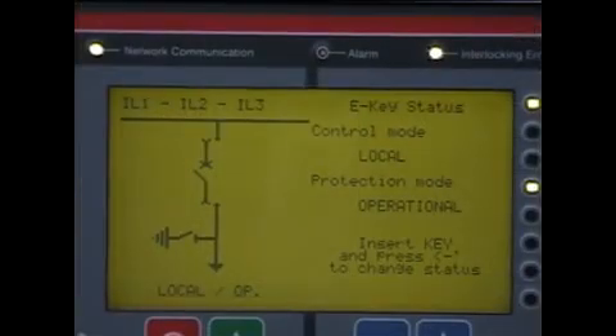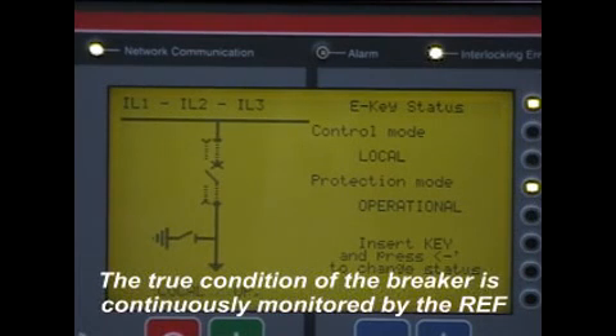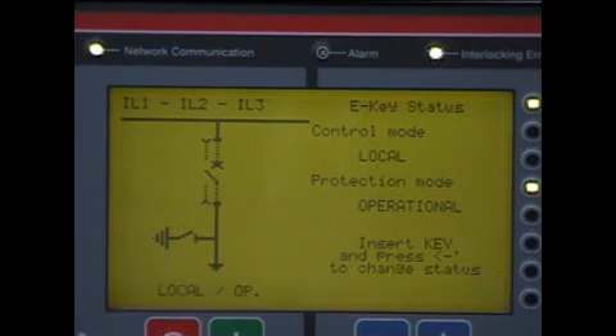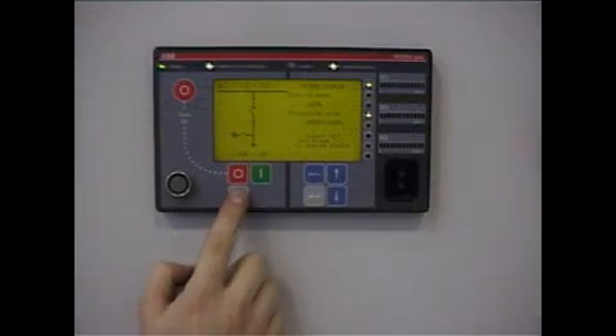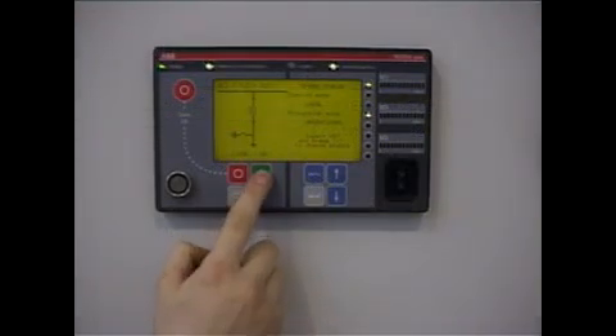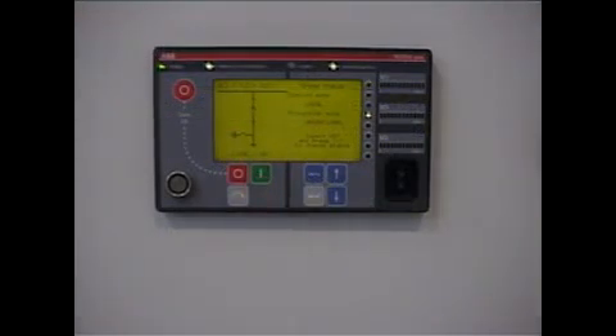This operation can also be monitored on the screen of the REF542 relay, where we see the circuit breaker in test position, in intermediate position, and finally inserted position. At this stage the circuit breaker could be closed and the load re-energized.